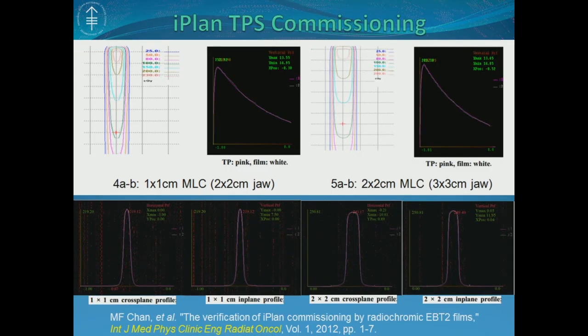Shown here is the film application in small field dosimetry, such as for iPlan commissioning. One can commission the iPlan MLC model, such as 1 by 1 or 2 by 2 cm MLC profile. And the dose can be exported from the triple channel and displayed in our in-house software display. This is a red channel display.